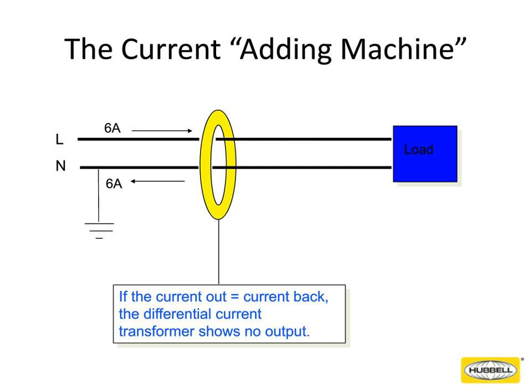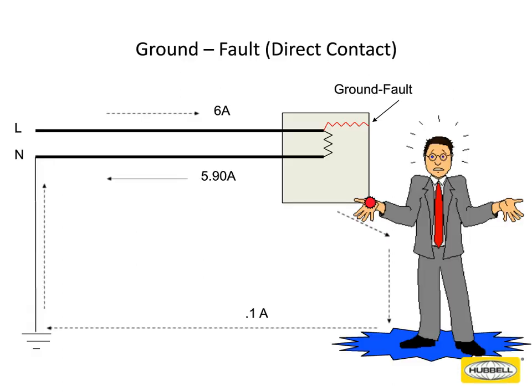So when we talk about the fact that a GFI trips in that 4 to 6 milliamp range, what we're talking about is if that load balance, if that 6 amps coming in isn't 6 amps coming back, then you've got a problem and the ground fault has to do its job and trip and take the power away from that circuit. So in this illustration here, you've got 6 amps coming in to your load. There's a ground fault that's occurred. You can see the person in the illustration is standing in some water. He has basically become the de facto ground to that situation. So that 0.1 amps of leakage is now going right through his body. He is becoming the ground, and if there's no ground fault receptacle present in that situation, then that person gets shocked.